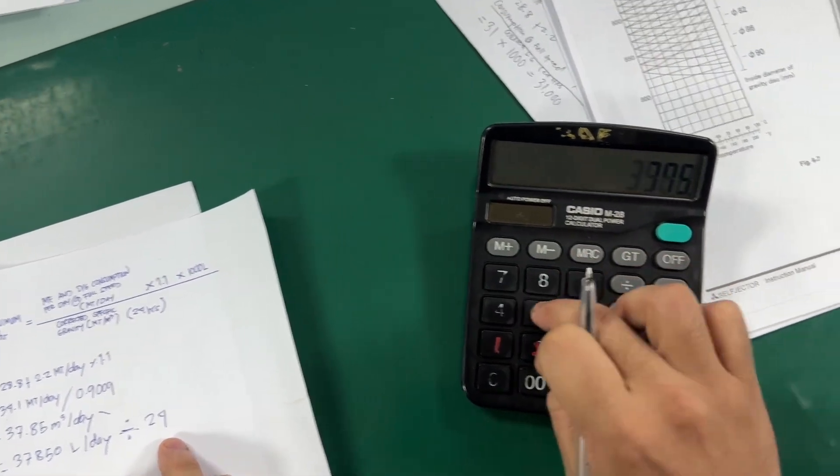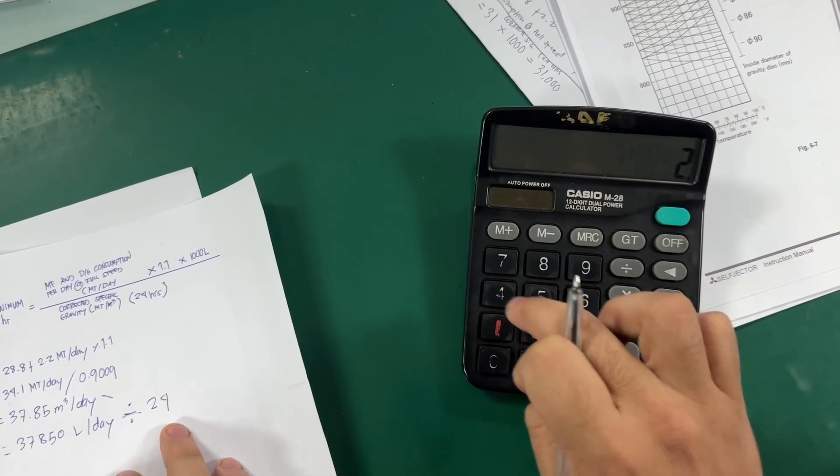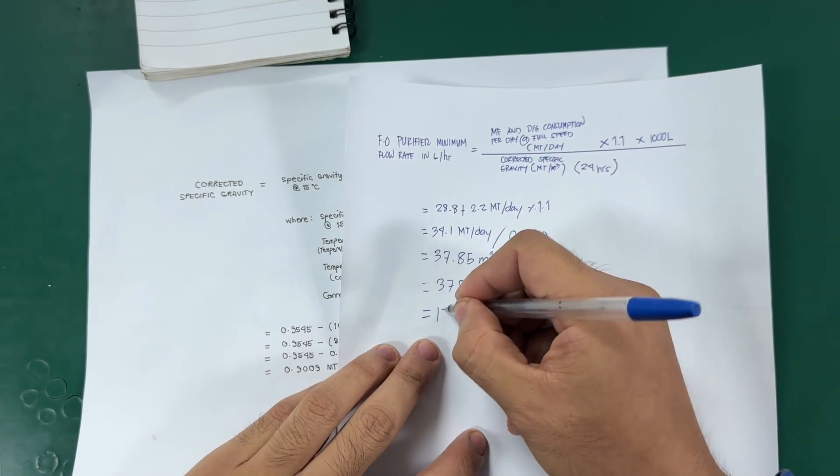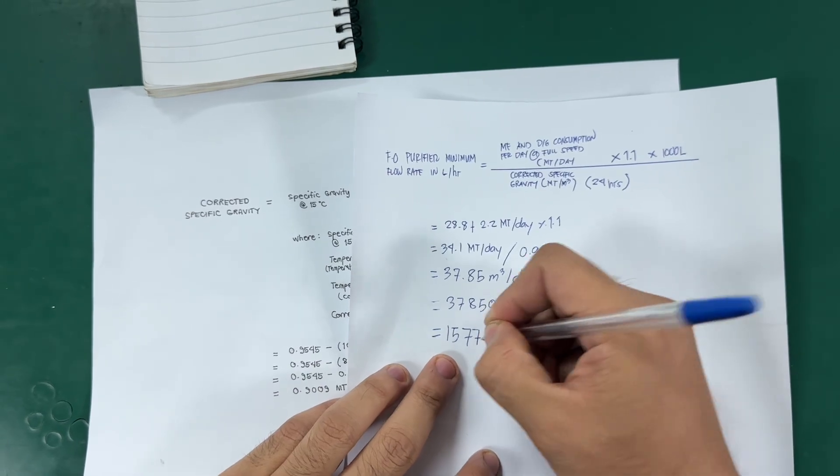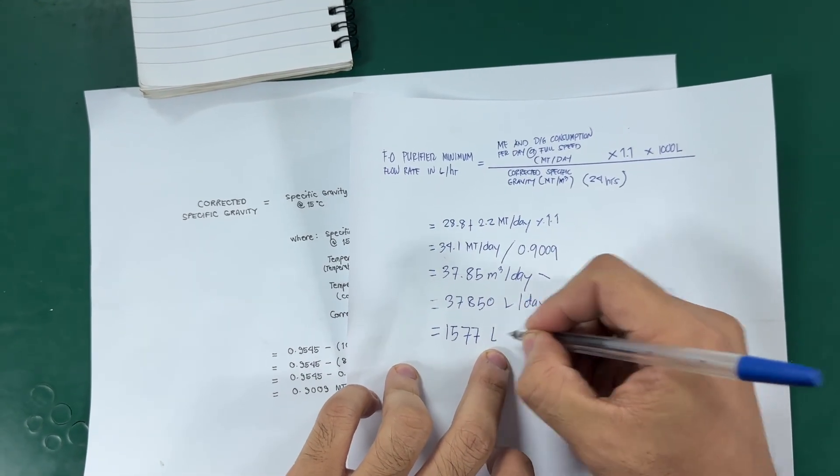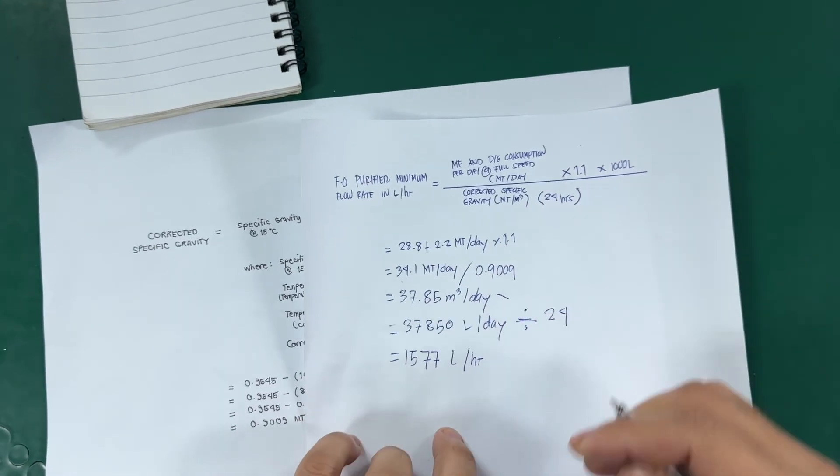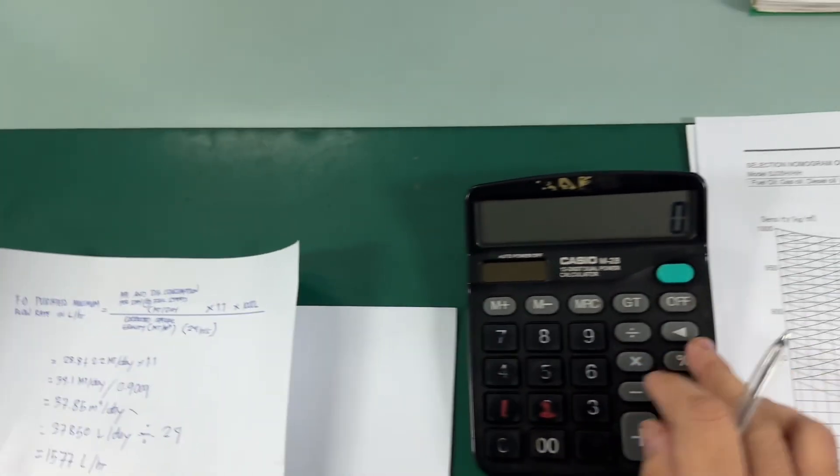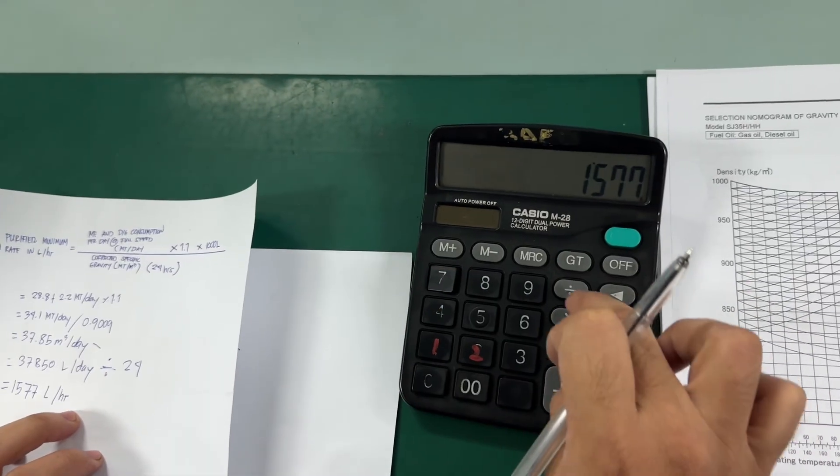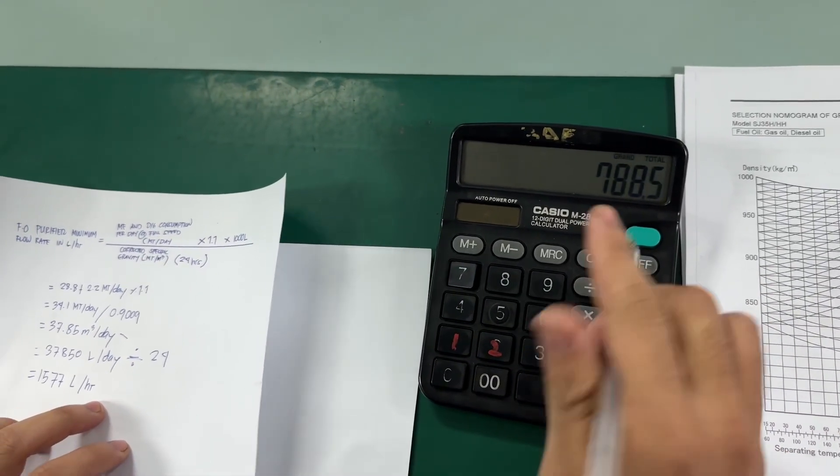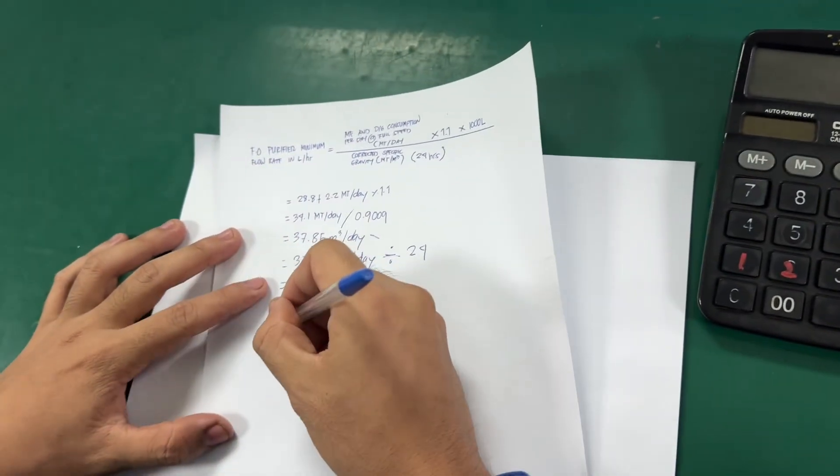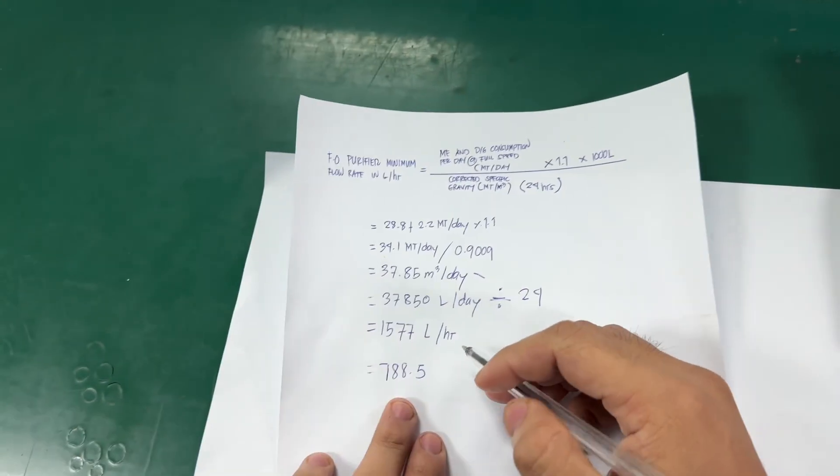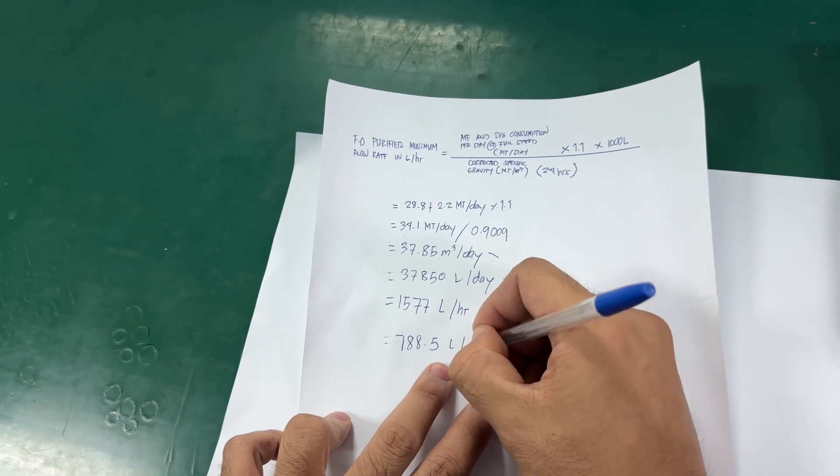37,850 divide 24 is equals to 1577 liters per hour. If our purifiers are running in parallel, we need to divide it by 2. 1577 divided 2 is equal to 788.5 liters per hour.